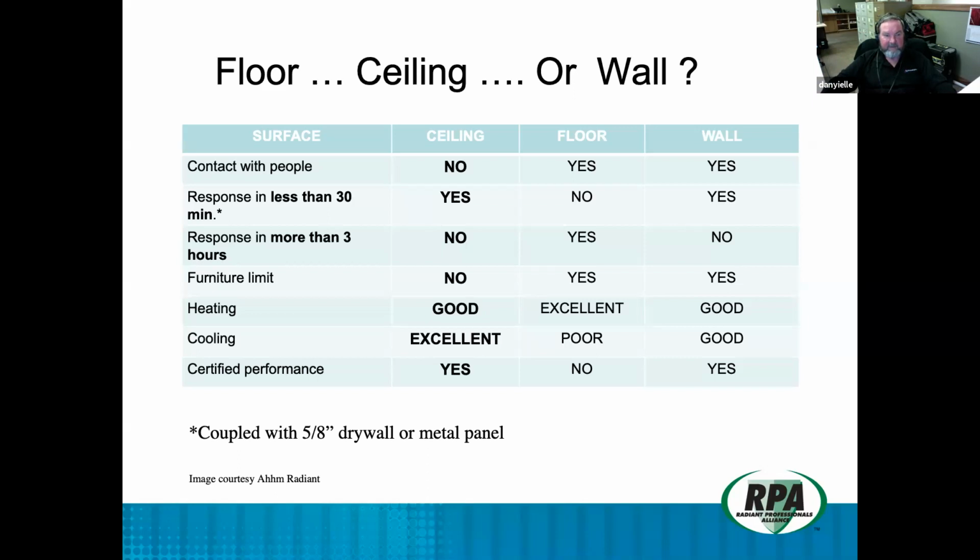But our recommendation is, hey, put a thermostat in there that is internet active, that you can turn this house up 2 days before you're going to be there. And when you show up, it will be perfectly comfortable, and you won't waste any energy to speak of. It's going to take whatever it needs to get to the condition that it needs. So absolutely, if they want radiant floors, talk them into an internet active thermostat that they can turn up 2 days before they're going to get there. And all the complaints about the radiant floor heating system not reacting quick enough are going to go away.